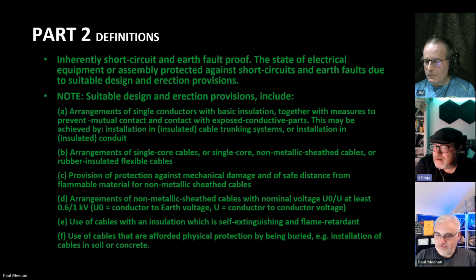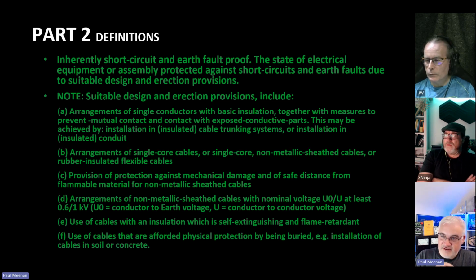I'm just trying to picture it. It's basically stating that the equipment or whatever you do will be resistant to earth faults and short circuits. That's how I'm reading that. Equipment or assembly protected against short. So you're not going to build an assembly where you've got a 20,000 amp fault current and it's only rated to 10, because it wouldn't be inherently.